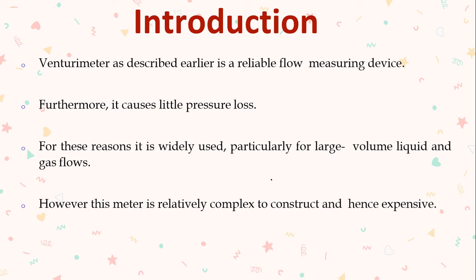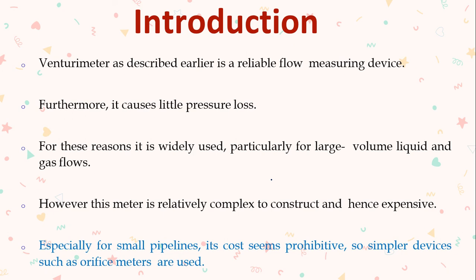Keeping all the disadvantages of the venturi meter in view, we can adopt an orifice meter. One more advantage of the orifice meter is the space it takes — since the venturi meter contains three components (convergent, divergent, and throat), it requires more area in a pipe, whereas the orifice meter requires less area. So wherever a venturi meter cannot be fixed, you can use an orifice meter. It is especially useful for small pipelines with less discharge.